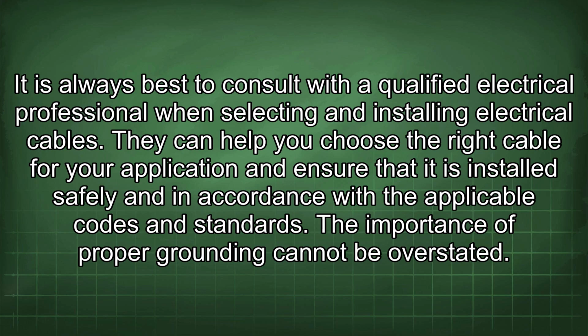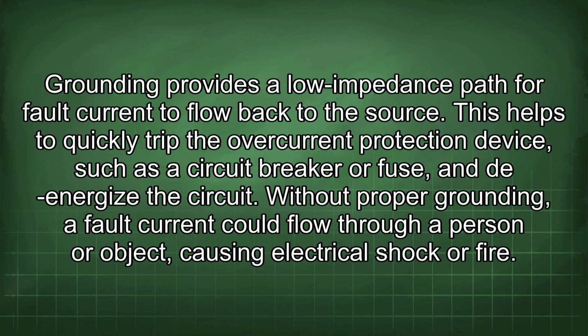The importance of proper grounding cannot be overstated. Grounding provides a low impedance path for fault current to flow back to the source. This helps to quickly trip the overcurrent protection device, such as a circuit breaker or fuse, and to de-energize the circuit. Without proper grounding, a fault current could flow through a person or object, causing electrical shock or fire.